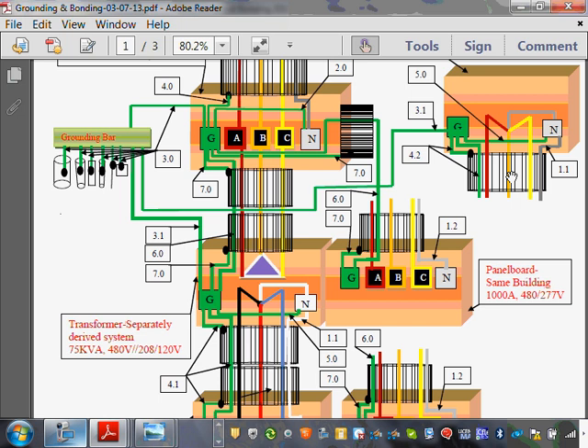One application I'm thinking of is a rental. You have a huge generator, for example, you drive a ground rod, and it's supposed to be rated with number 6, something like that. Instead of number 6, you've got a generator that's going to be there for a while. 250 kW size. Sure. Yeah, number 6, if it's solely just to the ground, number 6. Number 6 is your bare minimum. Permanently installed, we go larger than that.